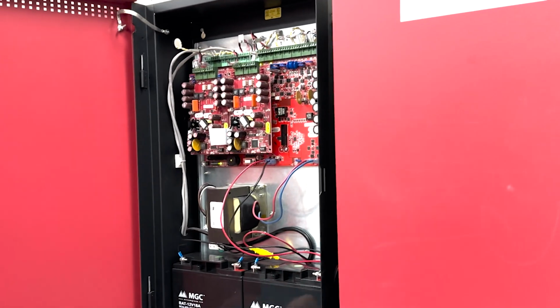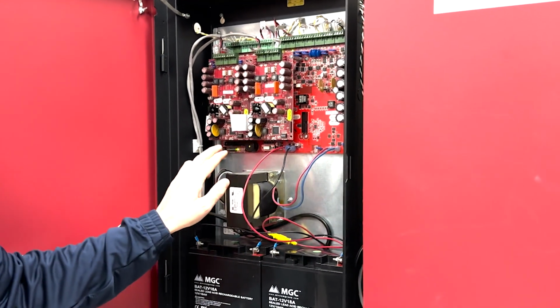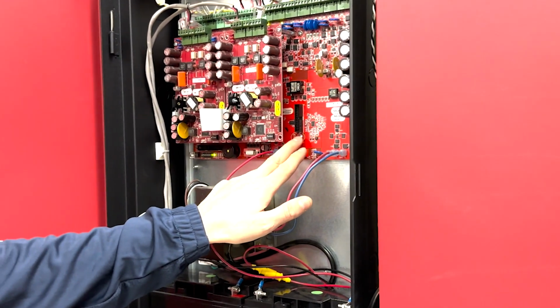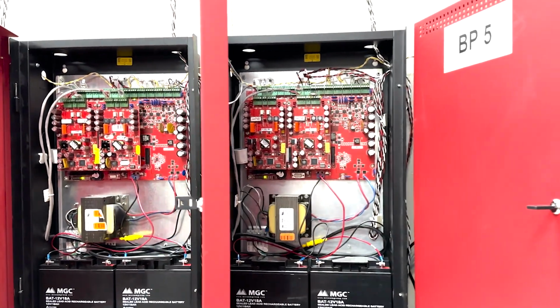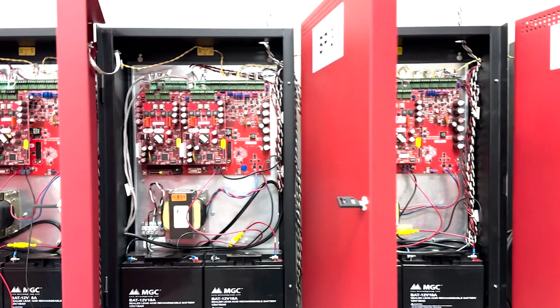The booster panels use the same mainboard MD1078, with provisions for 2 QAD30 amplifiers and 1 QAS 2x8 splitter. The booster panels allow support for a distributed audio system, and the panels act as subsequent followers to the main panel's functions. Up to 5 booster panels can be connected to a Secutron AUDMAX main panel.